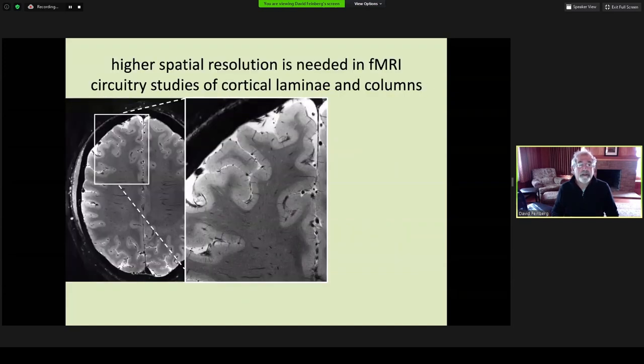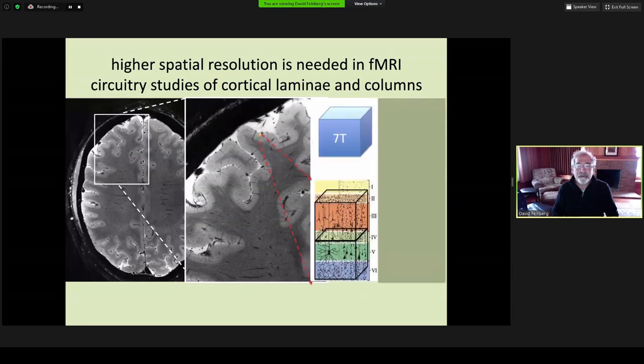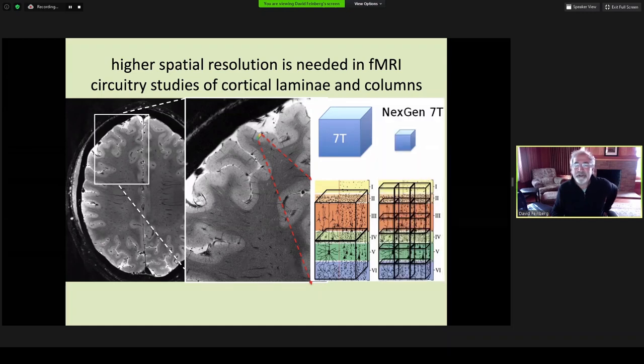Why do we need higher spatial resolution in fMRI circuitry studies of cortical lamina and columns? Currently, 7T provides down to about 0.75 isotropic resolution, which gives about two or three pixels across most cortex, which is two to four millimeters typically. Higher resolution with a next-gen 7T scanner will enable imaging with much less partial voluming of the layers as well as the pial vessels.